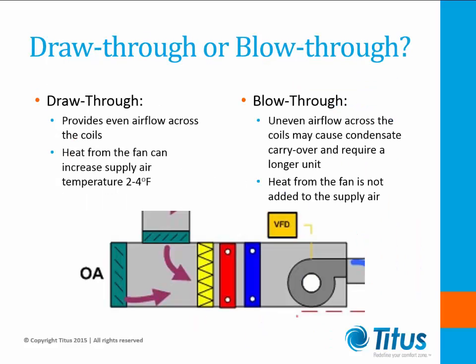Since we're on the topic of draw-through and blow-through, let's take a look at this next slide. Air handling units in which the supply fan is installed after the heating and cooling coils is referred to as the draw-through design. In a blow-through air handling unit, the supply fan is located prior to the coils. This arrangement allows fan heat, which can be significant at times, to be removed from the airstream without having to subcool the supply air as necessary for draw-through units. Although much less common, blow-through units do have applications, particularly in healthcare where IAQ is very important. We are also starting to see an increase in the use of low-temperature air systems.